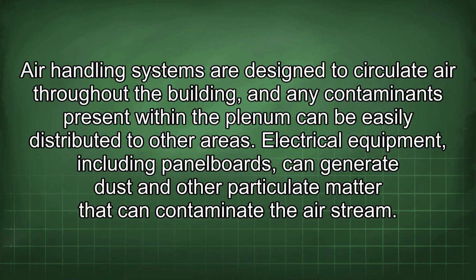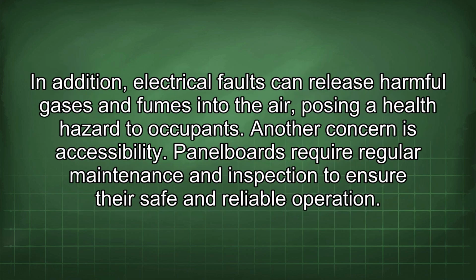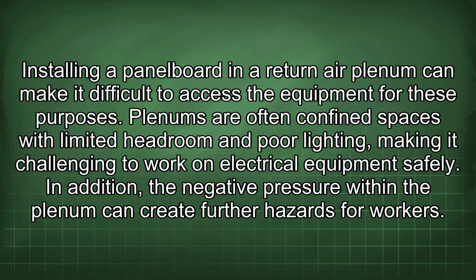Electrical equipment, including panelboards, can generate dust and other particulate matter that can contaminate the airstream. In addition, electrical faults can release harmful gases and fumes into the air, posing a health hazard to occupants. Another concern is accessibility. Panelboards require regular maintenance and inspection to ensure their safe and reliable operation. Installing a panelboard in a return air plenum can make it difficult to access the equipment for these purposes. Plenums are often confined spaces with limited headroom and poor lighting, making it challenging to work on electrical equipment safely. In addition, the negative pressure within the plenum can create further hazards for workers.